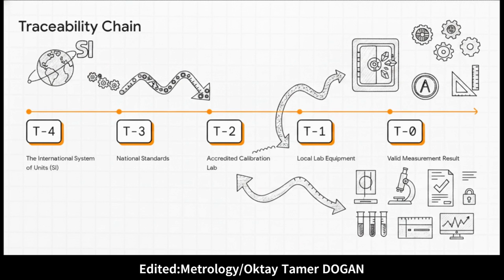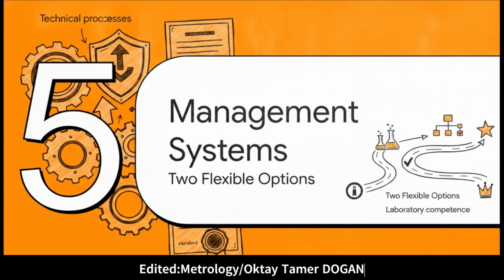National Metrology Institutes hold the national standards that realize these SI units. Then, those institutes calibrate the equipment of accredited calibration labs. And then, those accredited labs calibrate the equipment used in your local testing lab. This unbroken, documented chain of calibrations, with each link contributing its own evaluated measurement uncertainty, guarantees that the final, valid measurement result on your lab report is directly anchored to a globally agreed-upon truth. Pretty amazing, right?